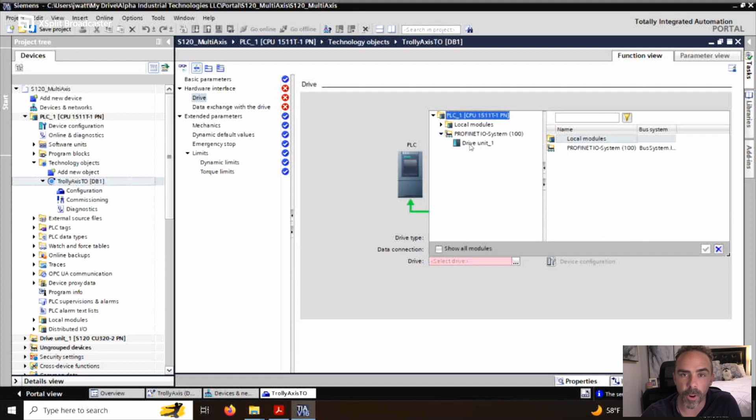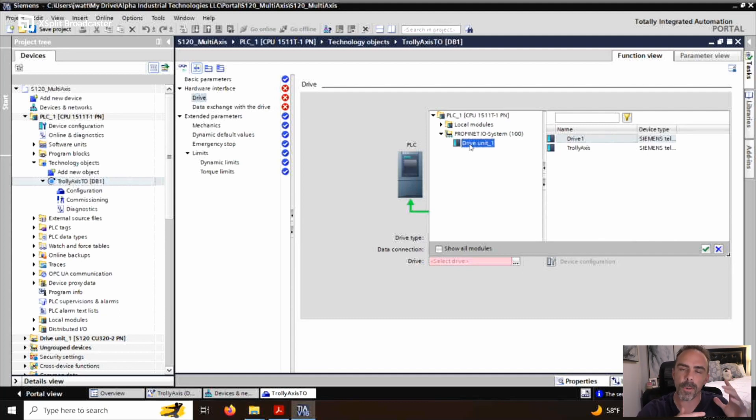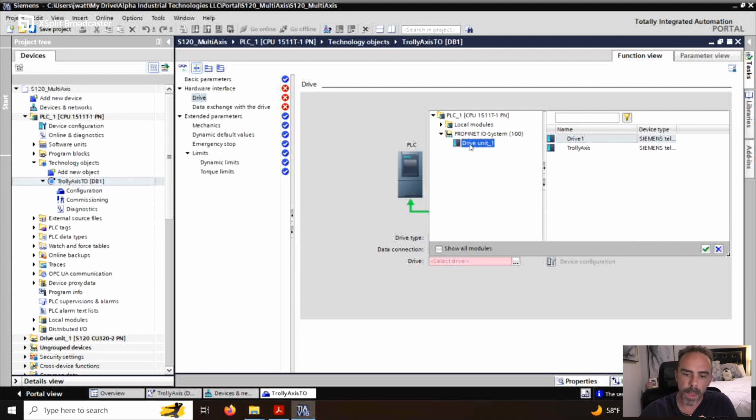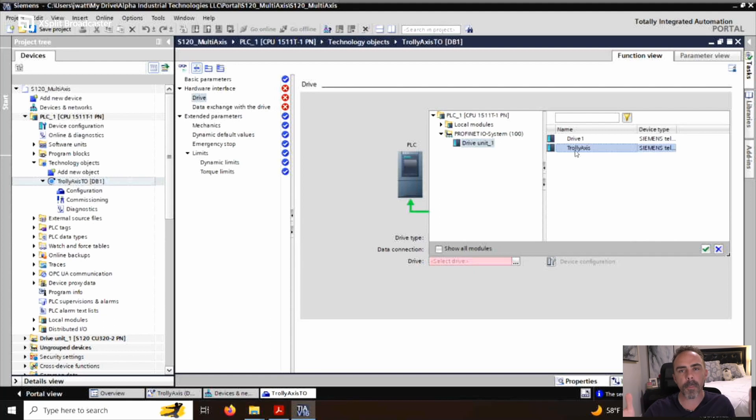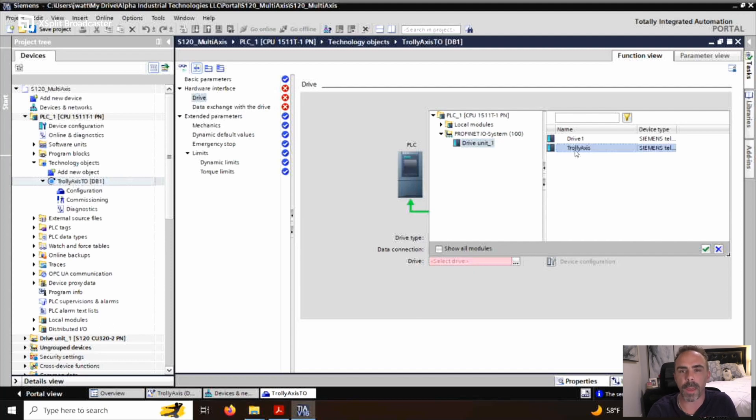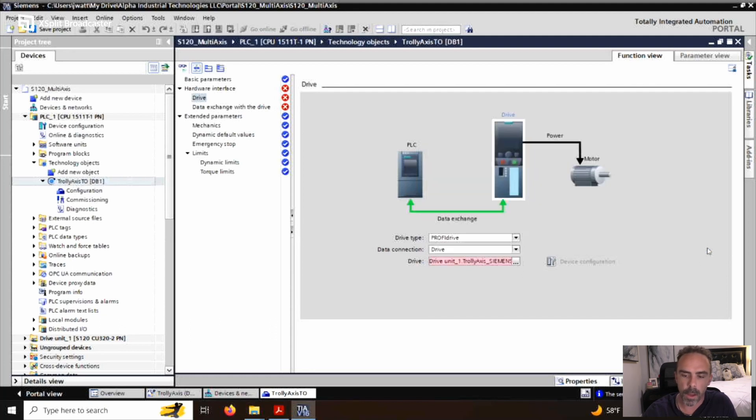And we have our drive unit one. Remember that drive unit one, that drive unit is the overall system that contains control units, line modules, signal modules, motor modules, all of that. For this one, I'm going to select this simple speed axis as the trolley axis. Because if you remember that trolley axis was just a vector control. So it was just an induction motor. So we're going to select that trolley axis and click on the check mark.